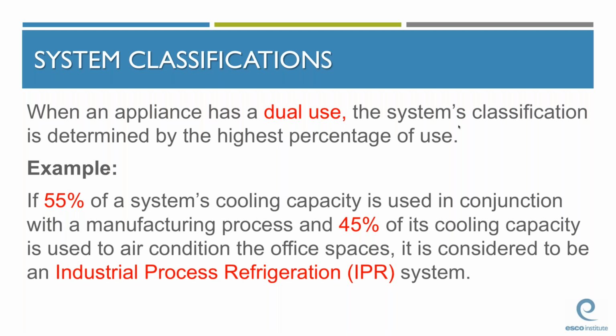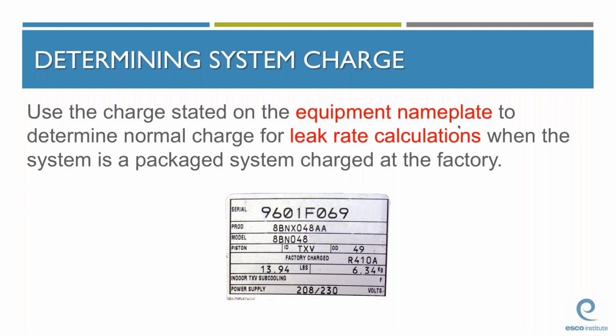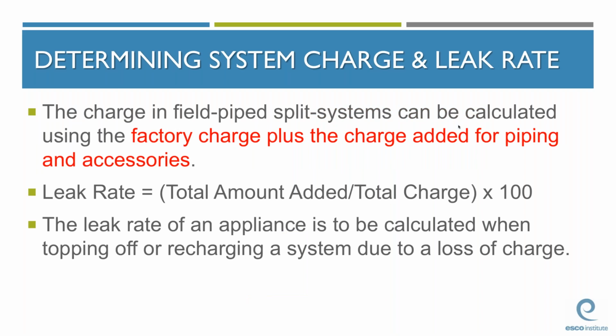This is important because the allowable leak rates are different for the three different system classifications. So now that we know how the systems are classified, the total system charge must also be known in order to determine if the amount of refrigerant that is leaked from a system is below the new limits. If the appliance is a package system, use the charge indicated on the equipment nameplate to calculate the unit's leak rate. The refrigerant charge for split systems can be determined by using the factory charge as the base and then adding to it any additional refrigerant that is required to compensate for refrigerant lines and piping accessories.